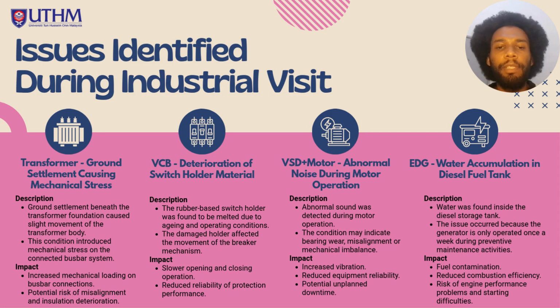So this slide represents the issues identified during our visit. Firstly, for the transformer, ground settlement causes movement of the transformer body, creating mechanical stress on the connecting busbar system. Secondly, for the vacuum circuit breaker, deterioration of the rubber switch holder results in slow opening and closing operation. Third, for the motor system, abnormal operation noise was detected, indicating possible bearing wear or mechanical imbalance.